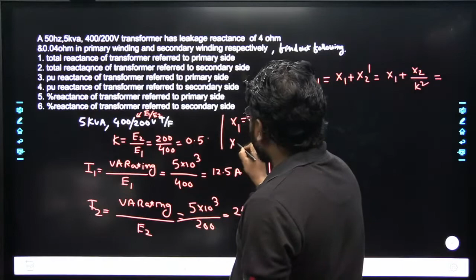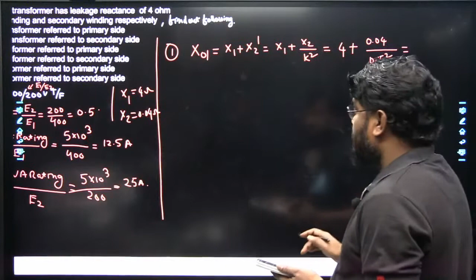Suppose it is a given rating of 5 kVA, 400 upon 200 volts transformer. So K is equal to E2 by E1, that is 200 divided by 400, which is equal to 0.5. Next, let us find the primary current. That is the VA rating of the transformer divided by the EMF induced in the primary winding, so 5 into 10 to the power of 3 divided by 400, which is 12.5 amps.